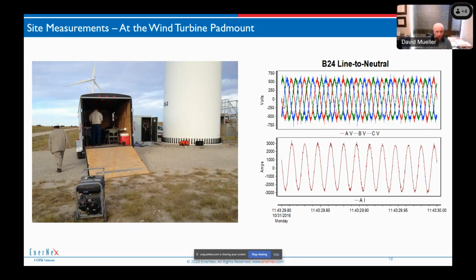But can that affect transformers? Well, if the electrostatic shielding isn't what it needs to be, if the insulation isn't what it needs to be to handle these types of considerations, then that might be taxing. But for this report and other reports, what I've said is, was the manufacturer of the transformer told that it was going to be used on a wind turbine inverter?